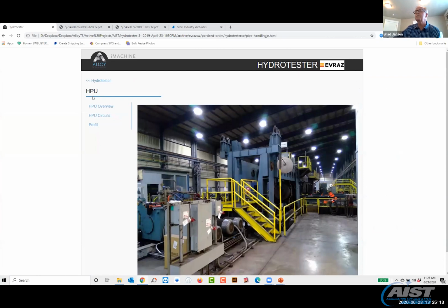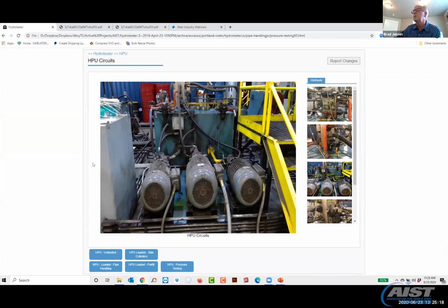Here's the hydraulic power unit. You can see from this, I'm going to go down. The HPU, the hydraulic power unit, in and of itself has different events that it can be in. It can be either loaded or unloaded. And as I click on those circuits, this one is unloaded. And this, by the way, this HPU runs the framework, and it also is powering the incoming pipe controls.